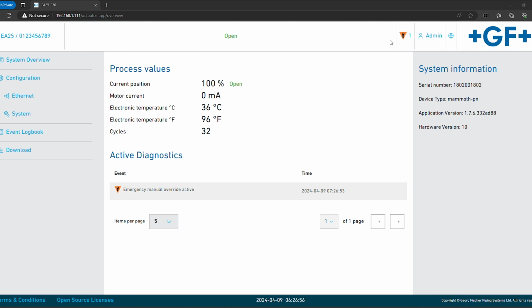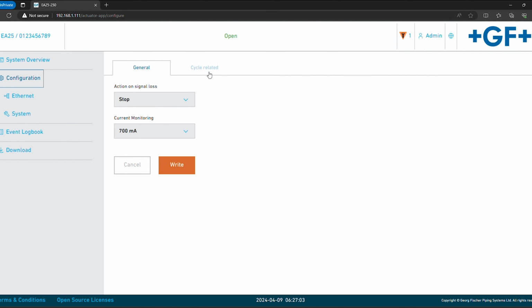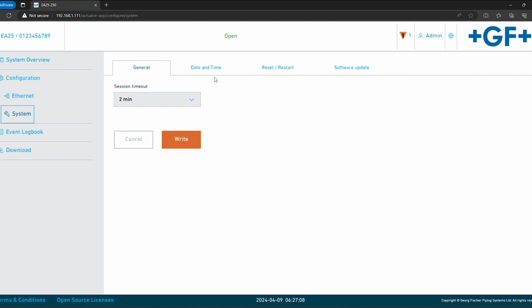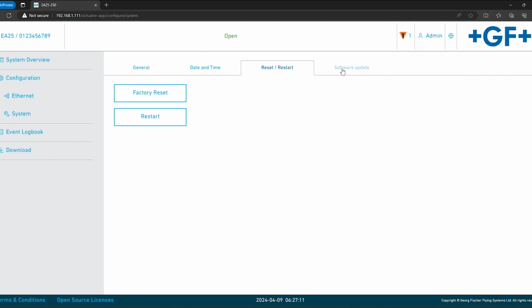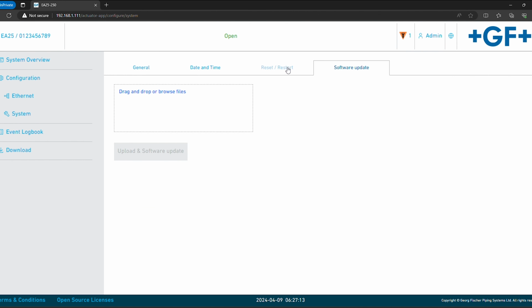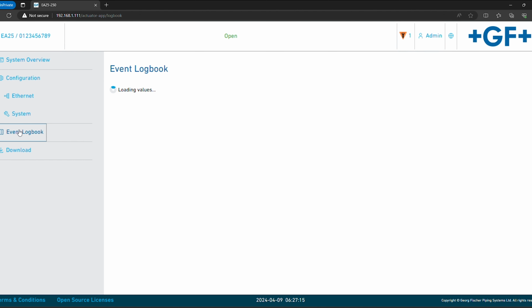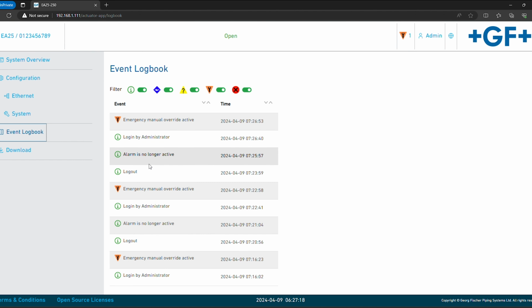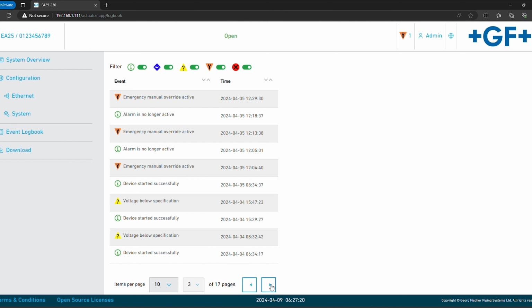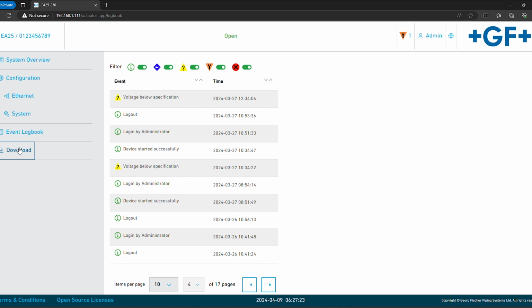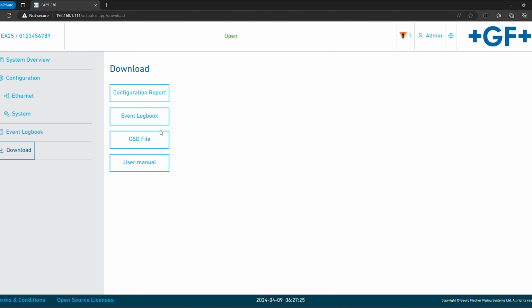Diagnostic events are visualized by NE107 status, a clear description of the event, and the timestamp of the occurrence. Configuration of motor current and cycle time allows a process-specific monitoring. Factory reset, restart, and even firmware updates, everything is possible without direct device access. The event logbook tracks up to 5,000 device events, which includes both diagnostic events and general events, such as parameter changes.